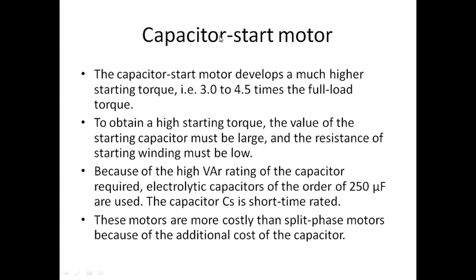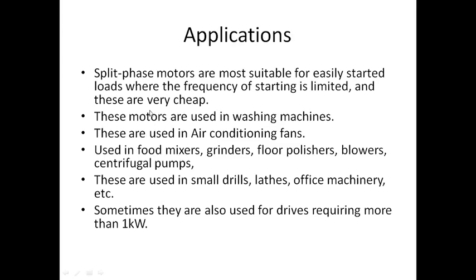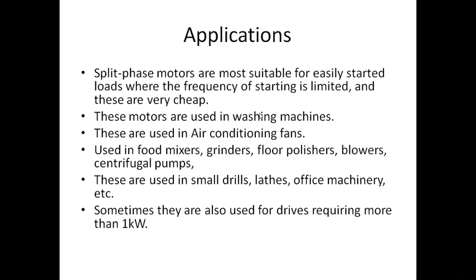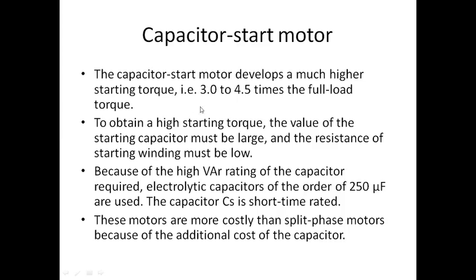Next is your capacitor start motor. You are going to introduce a capacitor in your motor. Why go for this? In the split motor, your torque is very less, only 1.5 times full load torque. I want somewhat higher torque, that is 3.0 to 4 times the full load torque. So I want to increase my torque, and to obtain high torque, I'm going to introduce a capacitor to my motor.